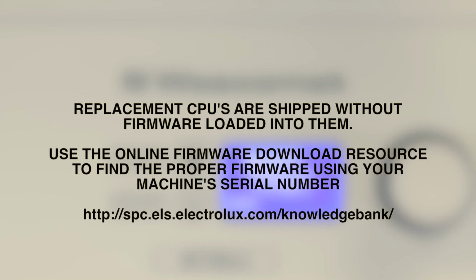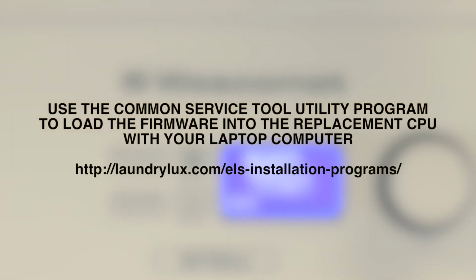Note that replacement CPUs are shipped without firmware loaded in them. You can use the online firmware download resource to find the proper firmware using your machine's serial number. Use the Common Service Tool Utility program to load the firmware into the replacement CPU with your laptop computer.